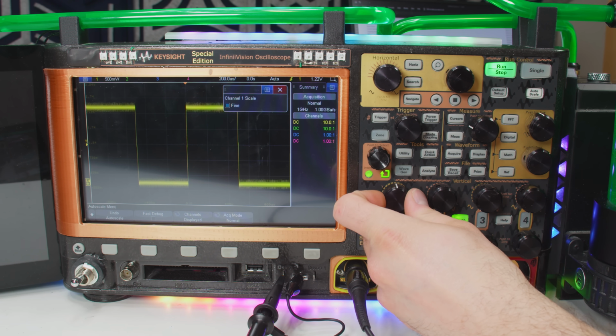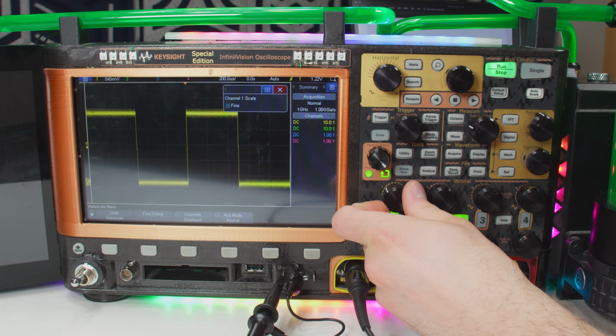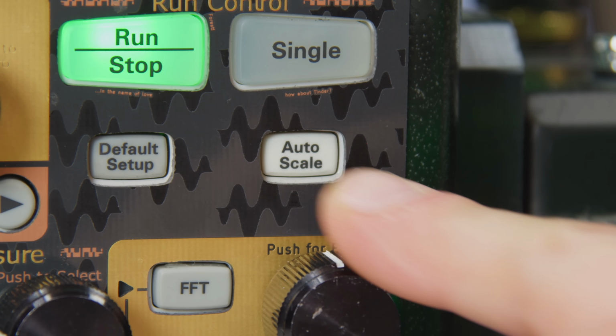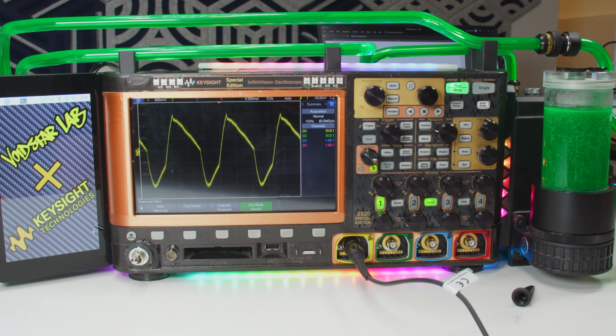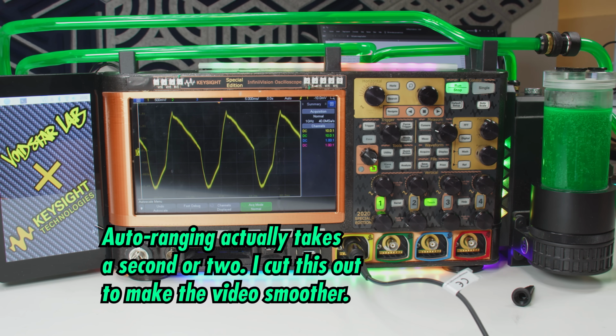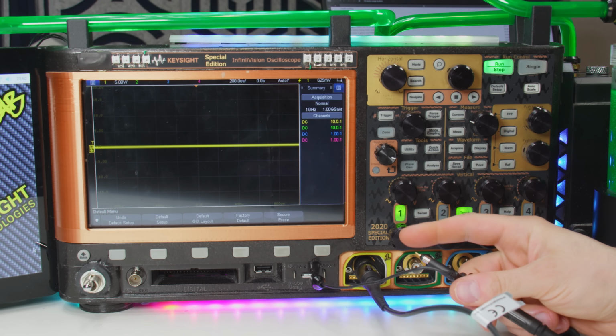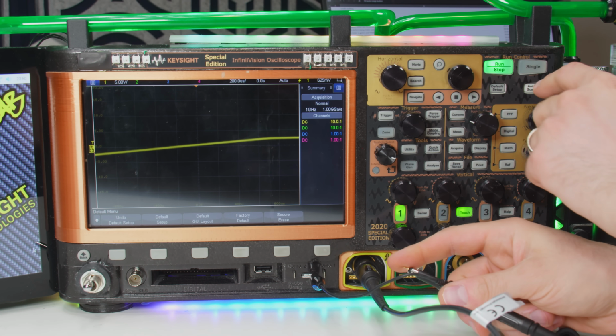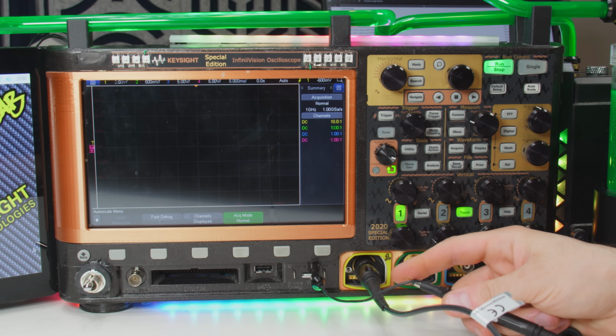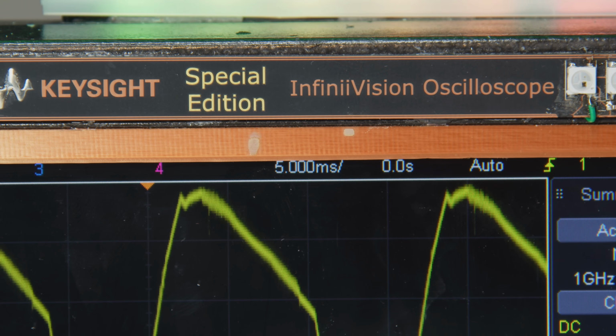If your signal is consistent, you can even have the scope do this all for you. Just hit auto range and it'll tune itself to fit the whole curve on screen. Just don't trust anything automatic too much. If the signal is erratic or if it's pure noise, it'll still auto range itself just against interference, usually 50 or 60 hertz hum coming from the walls. The wires in the walls, not the walls themselves. This is a 60 hertz ghost!